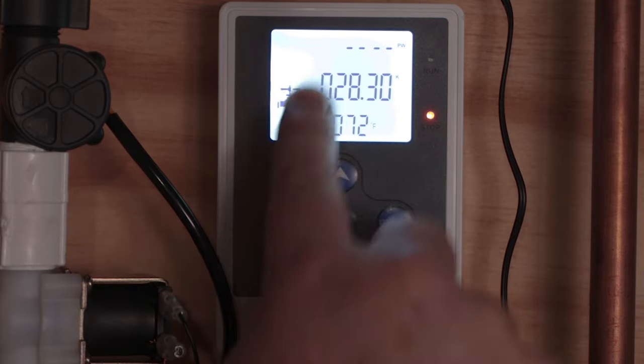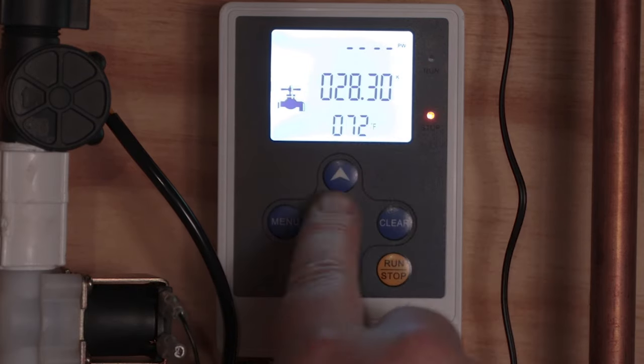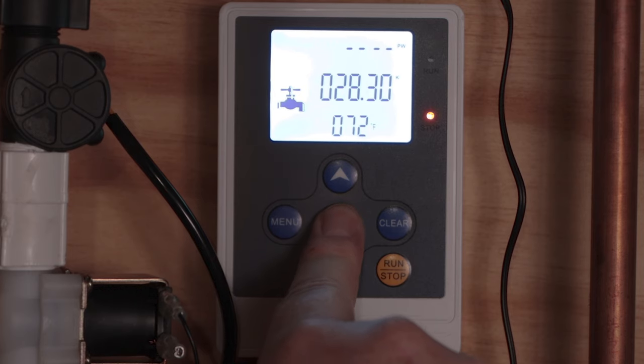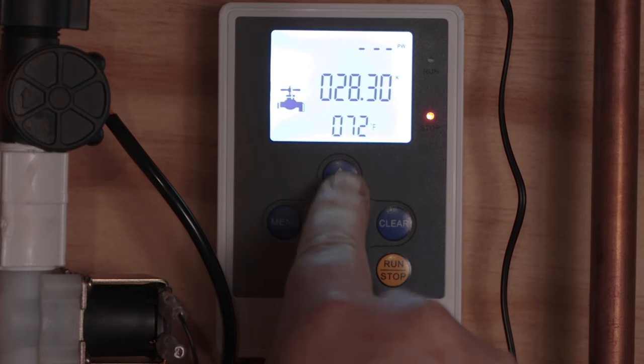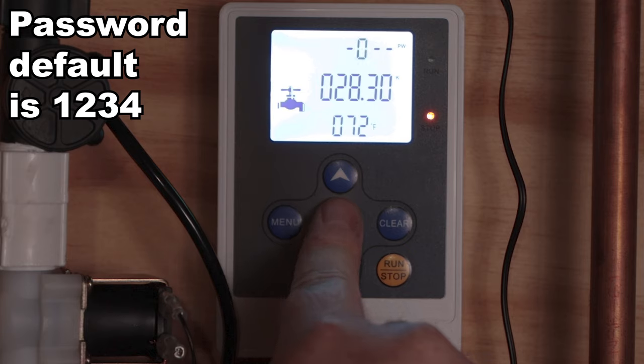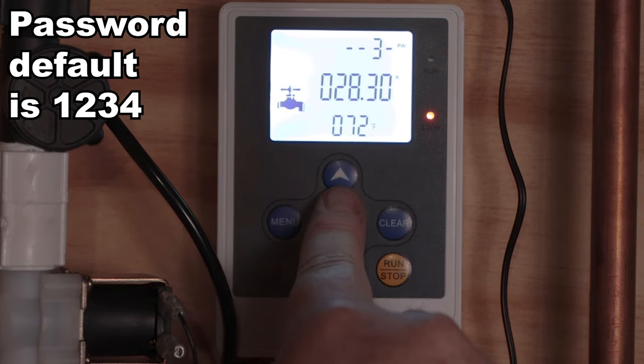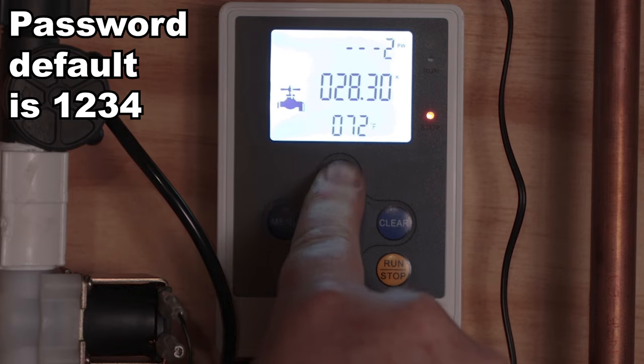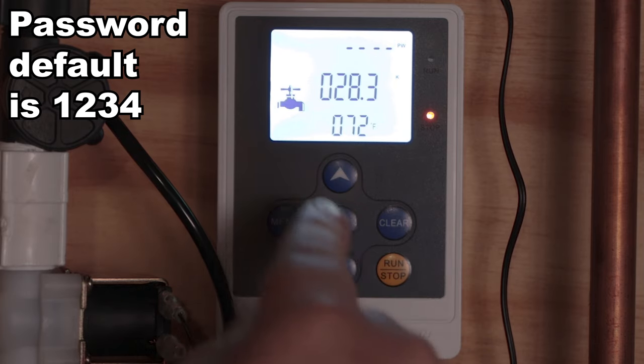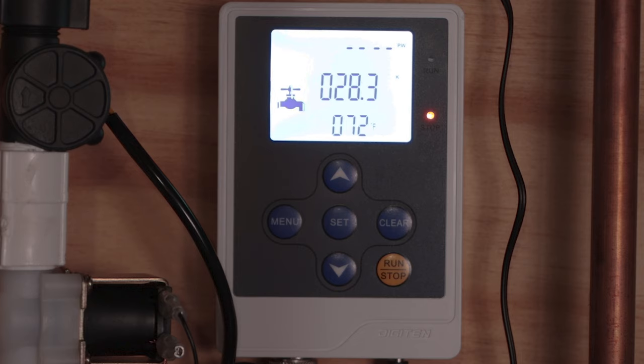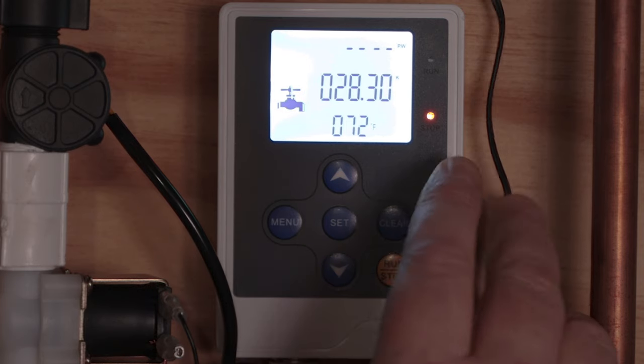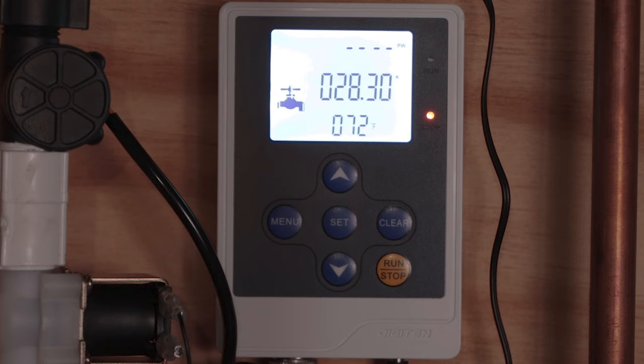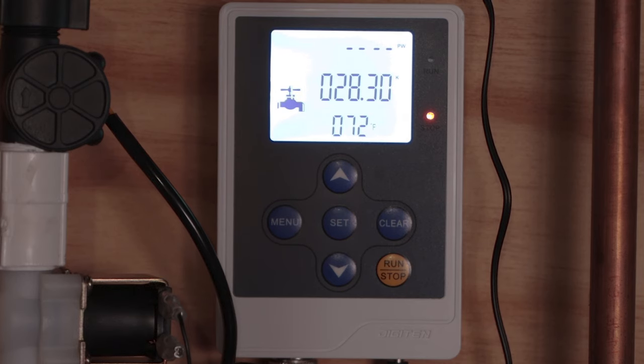Now the way that you change this is when you get to this password, you're going to press and hold the set button down. And then you're going to go one, set button, two, set button, three, set button, four, set button, and then it will let you change the K value. So this is a setting that I would advise you could probably start with this 28.3 K. And that actually was able to exactly dispense one gallon. And I'll show you that here in just a few minutes.